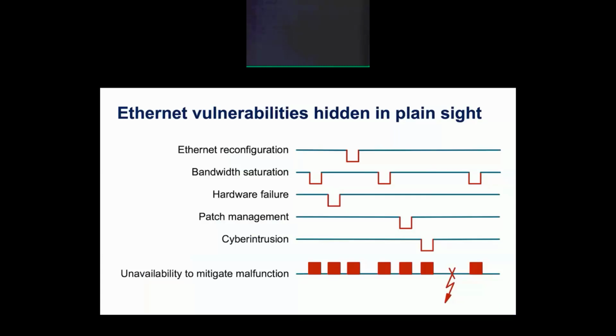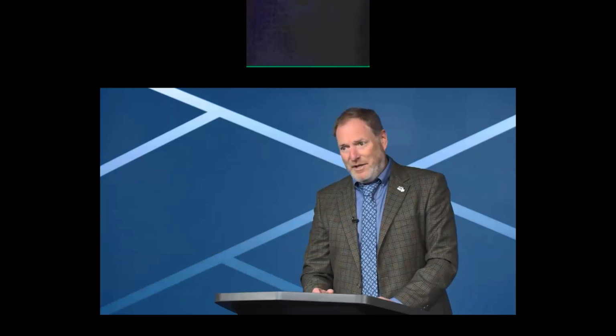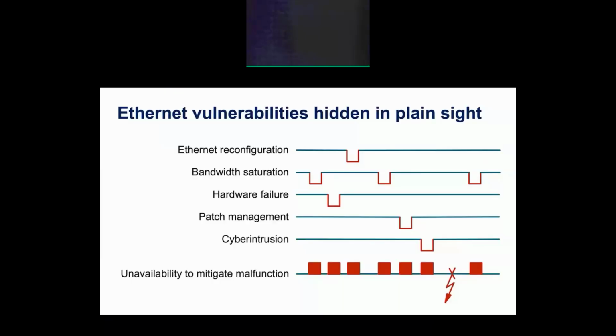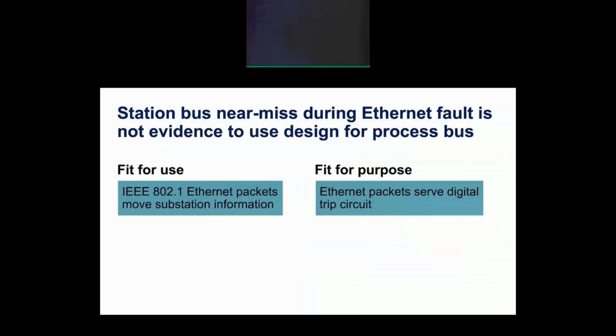Networks can be unavailable due to component failure, lightning, or other events. However, IT Ethernet creates an entire new suite of failure modes as a byproduct of adding flexibility. These failure modes exist by design and cannot be eliminated. They can only be reduced through sophisticated engineering practices, and they are the biggest culprit hidden in plain sight. And when any of these faults is present, the trip circuit message will not get through and the trip circuit will not function.